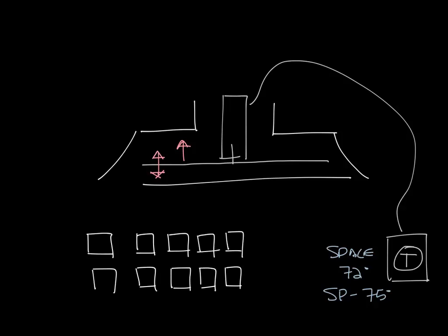But if all those diffusers are VAV diffusers, and now they're providing more airflow to the spaces, they'll start closing off too. So now we're looking at these closing off, and then these getting too cold and closing off. Now you have a lot of air trying to go through these diffusers that are closing off. And now the diffusers will start getting loud, and you have a system issue. So you have to provide pressure relief at this point.